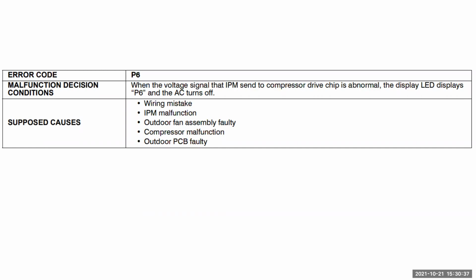So they run at different speeds. The best way, if you're going to check and see without pulling out the refrigerant, is what your temperature drop is across your coil. So on the P6, you also want to check and be certain your low pressure switch didn't get, hang on here.